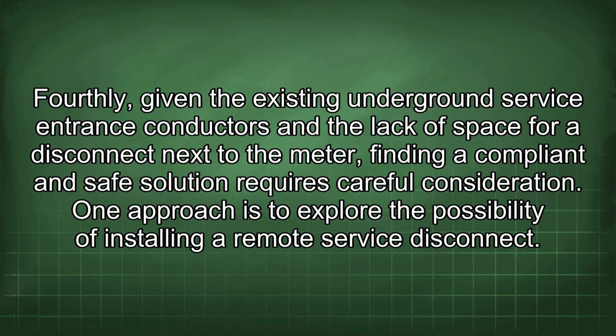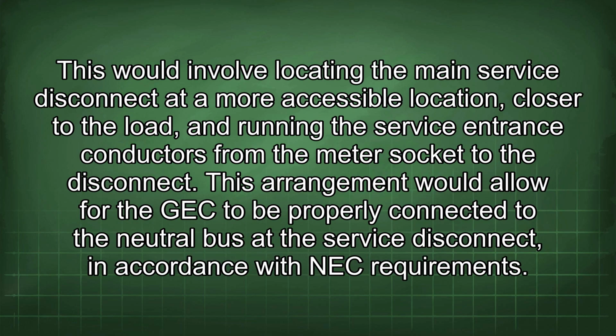Fourthly, given the existing underground service entrance conductors and the lack of space for a disconnect next to the meter, finding a compliant and safe solution requires careful consideration. One approach is to explore the possibility of installing a remote service disconnect. This would involve locating the main service disconnect at a more accessible location closer to the load and running the service entrance conductors from the meter socket to the disconnect. This arrangement would allow for the GEC to be properly connected to the neutral bus at the service disconnect in accordance with NEC requirements.